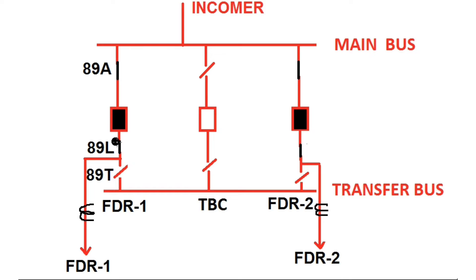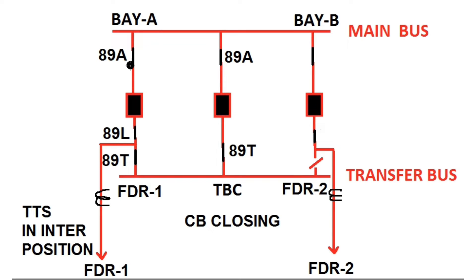Now, due to an online condition, this bay needs to be diverted to the TBC breaker. There may be a problem arising in this bay — either in 89A or 89L within this location — or this breaker needs to be shut down for maintenance purposes. So as the problem arises in this bay, during online condition feeder 1 needs to be diverted to the TBC bay.